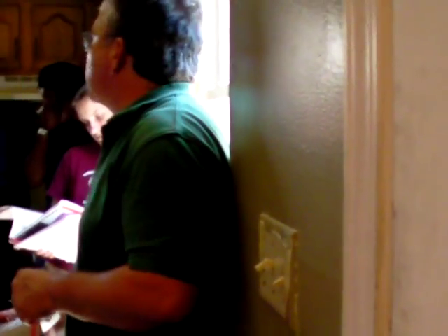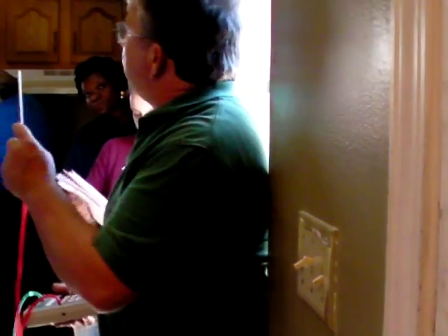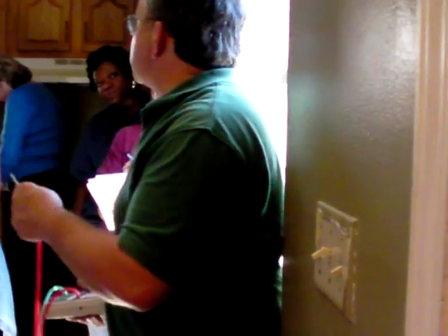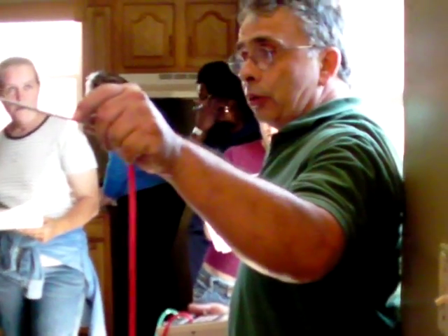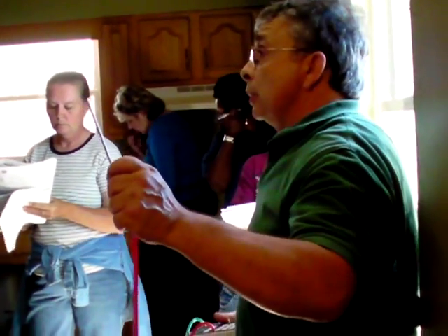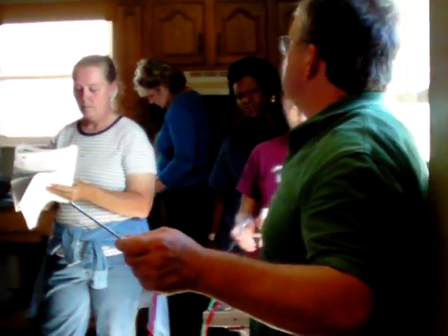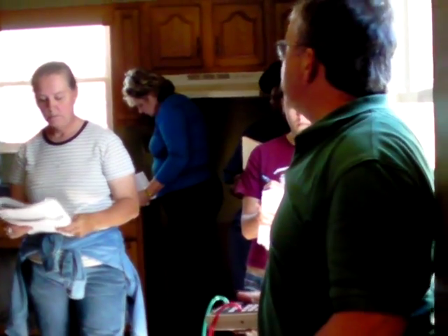Since I'm only showing about -1, -1.5, I'm safely below that 5. I'm even safely below that -2. If I want to keep in my head, this water heater today should really pass, and yet it's under a strain to pass today because it doesn't have extra heat from the furnace to help it, and it makes a very weak draft.